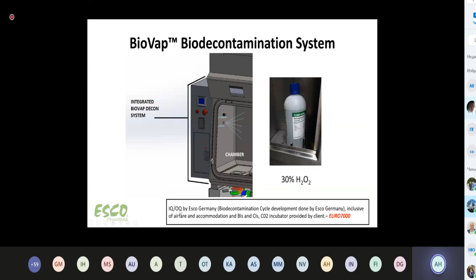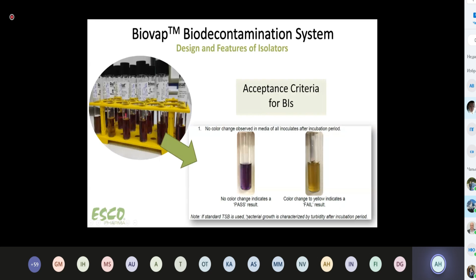IQ/OQ is similar to on-site testing, validation, commissioning. And this would be the test result. So we have two kinds of tests that we do for biodecontamination. To see the result, we need to have a biological indicator. If the biological indicator stays purple, it's okay, pass. If the color changes to yellow, fail. This is the biological indicator. You have to use an incubator to check for this. You got to grow this indicator.